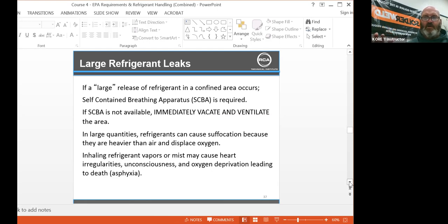Refrigerant techs will be in a motor room. The refrigerant blows. They try to stop it. The refrigerant is inhaled. They get dizzy. They pass out. They fall to the floor. That's because refrigerant is heavier than air. It actually pushes the oxygen out, and the technician dies. It's really fast. So if it blows, get out of the area. Your life is not worth trying to save $100,000 worth of ice cream. We value you way more than ice cream.